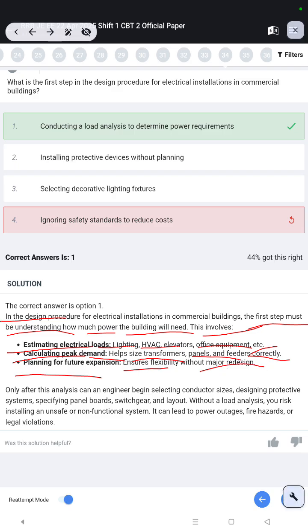Only after this analysis can an engineer begin selecting conductor size, designing the protective system, and specifying panel board, switchgear and layout. Without a load analysis, you risk installing an unsafe or non-functional system. It can lead to power outage, fire hazard, or legal violations.